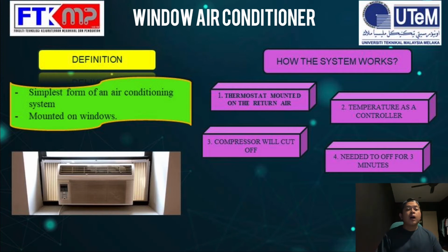Alright, so how the system works. The first step is the thermostat is mounted on the return of the unit, and the temperature is used to control the on and off of the compressor. Once the temperature has been achieved, the compressor will cut off by itself.